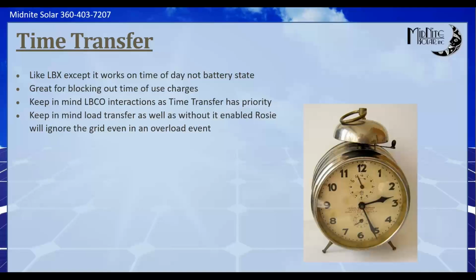It's not going to reconnect to that grid because it believes you don't want it to, because we've told it to not connect at any cost. So we need to make sure we enable that load transfer, and we turn the load transfer watts all the way up. And what that does then is, so say you set it for 7,000 watts on the load transfer. If the Rosie hits 7,000 watts, it will transfer over to the grid. When the wattage falls below 7,000 watts, it starts a 5-minute timer, and then it connects back to the grid.